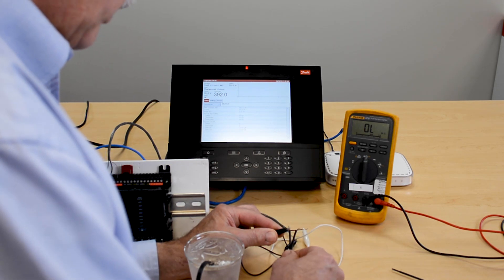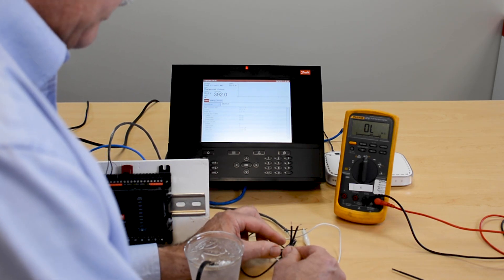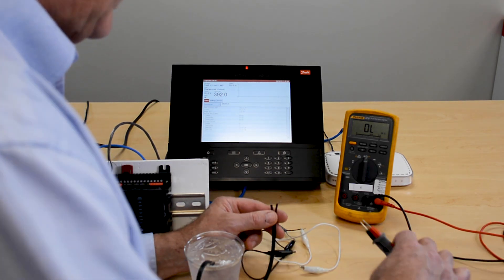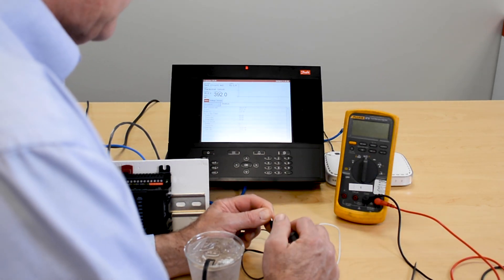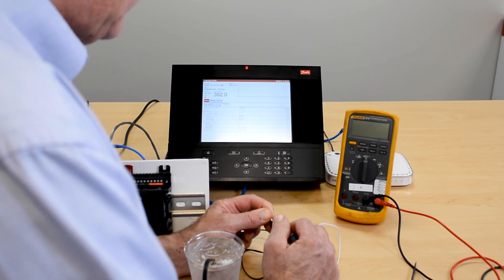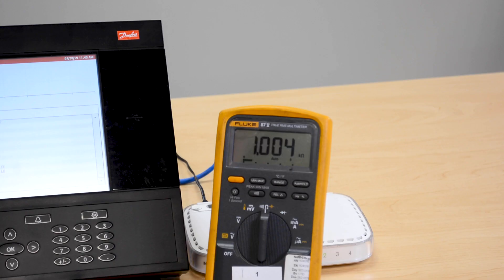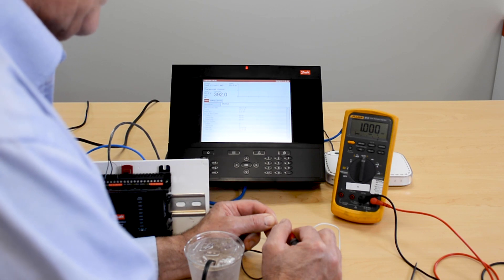The other thing we can always do is take our leads to our meter. If we go across the two leads, we're going to see our ohm reading being 1000 ohms. That's exactly what we're expecting, which is an indication that we are right on money when it's a medium temp case in a 32-degree environment.